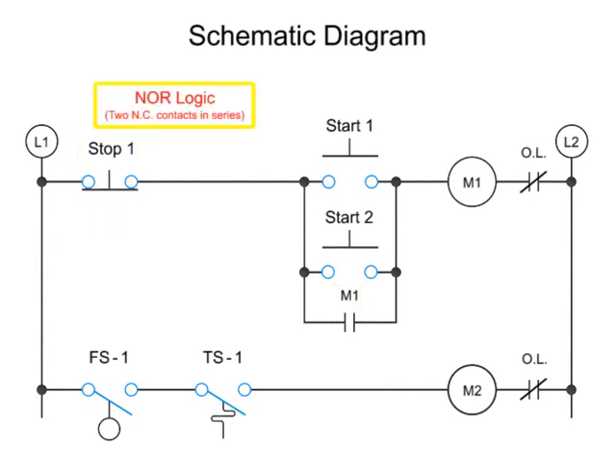NOR logic, an extension of NOT logic, operates by the inclusion of a second normally closed push button in series. In this arrangement, pushing stop button 1 or stop button 2, the M1 coil is shut off and the M1 holding contact is deactivated.